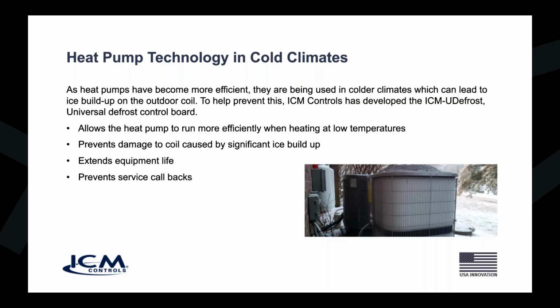Just like in your refrigerators, how you have a defrost cycle in your freezer, that's there for a reason as well. Because if you didn't have that defrost control in the freezer of your refrigerator, you'd have a block of ice inside your refrigerator, and in the old days, you used to have to defrost your freezer. You'd open up the door and just let it unthaw, so to speak. Nowadays, they have defrost controls in your refrigerator that prevent freezer frostovers. Same idea here. So this allows the heat pump to run more efficiently when heating at low temperatures, prevents damage to the coil and ice buildup, extends the equipment life, and prevents service callbacks. That's what defrost boards do.